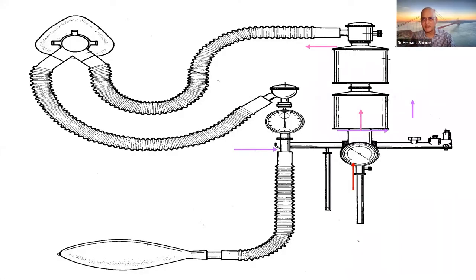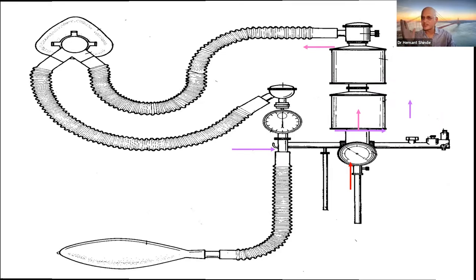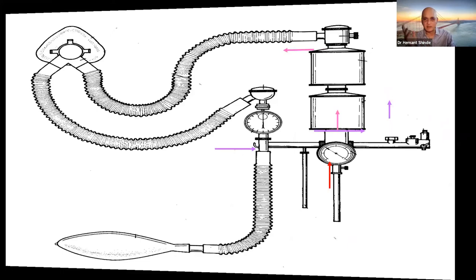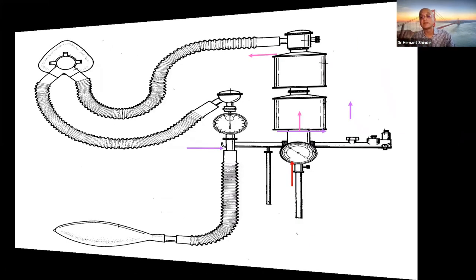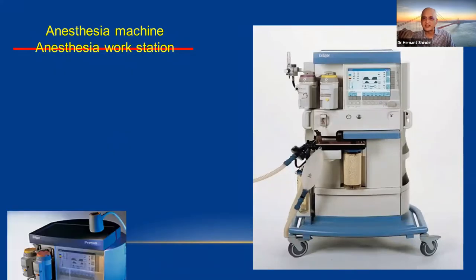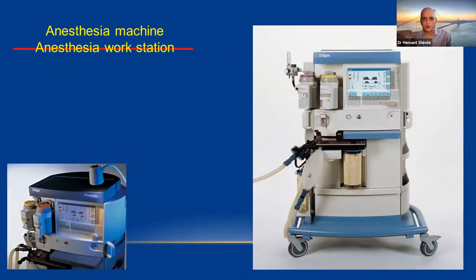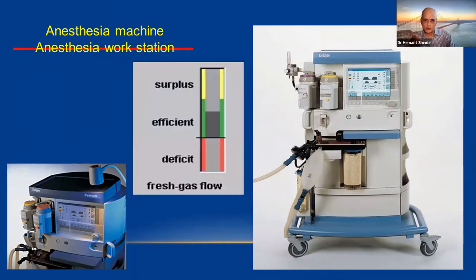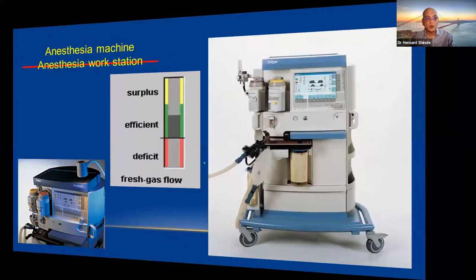Today, any anesthesia machine — whatever the make — essentially has an inspiratory limb, expiratory limb, pressure valves, soda lime canister, and pop-off valves. Modern high-tech machines are now called anesthesia workstations. Some have excellent features, like the econometer on the Dräger machine, which shows whether your flows are surplus (yellow zone), efficient (green zone), or in deficit.